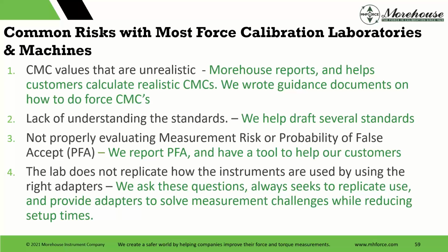A common risk with most force calibrations is CMC values that are unrealistic. We find this all the time. I need to do a class on it, where I have scopes I've collected where the CMC values are better than NIST. And now that Patrick is an accredited auditor and works for A2LA, he can go sniff those out and correct those where the CMCs are better than NIST. That's a fun one. Another risk is a lack of understanding of the standards, and that happens. There are people on standards committees who just do things wrong because, process-wise, they can do more calibrations if they just ignore it or take exception to it, even though the standard says things like "in no case shall."